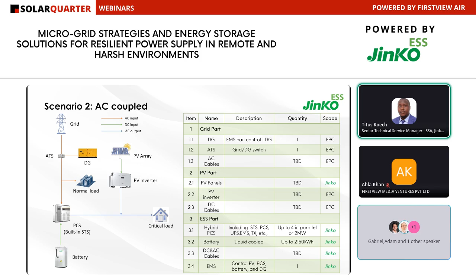For the AC coupled scenario, we've given flexibility to integrate with any PV inverter available in the market, as long as we know the communication protocol and have the register map. We can then embed this into our EMS to control the PV inverters. In this case we only have the PCS without combiner boxes, and the PV is connected on the load side of the PCS through the PV inverters.